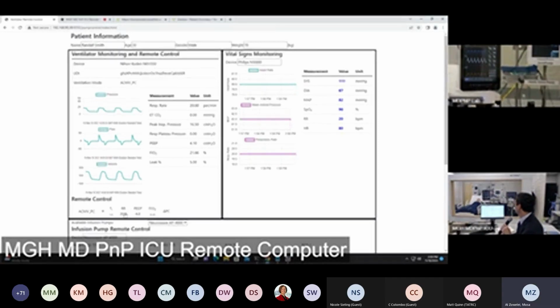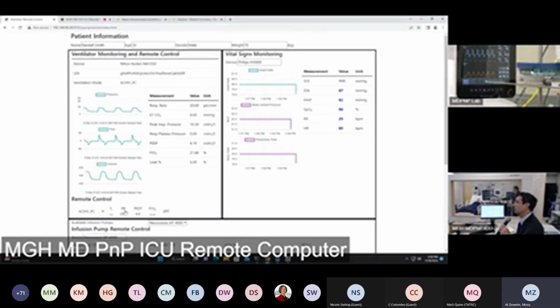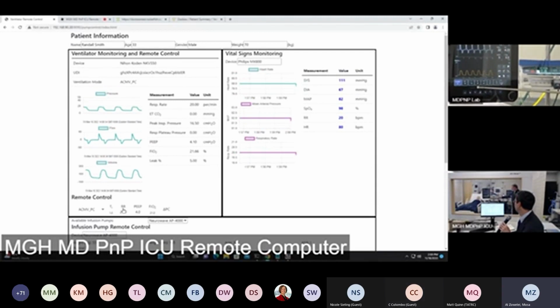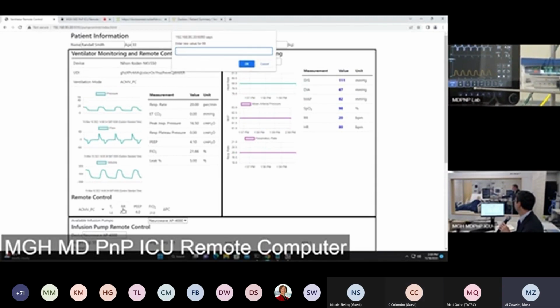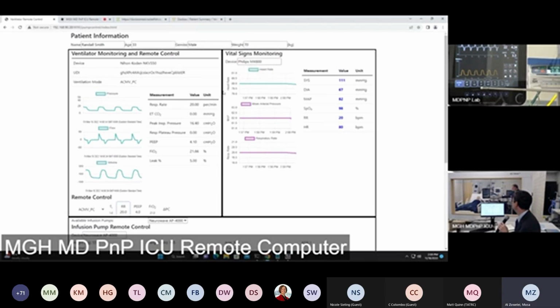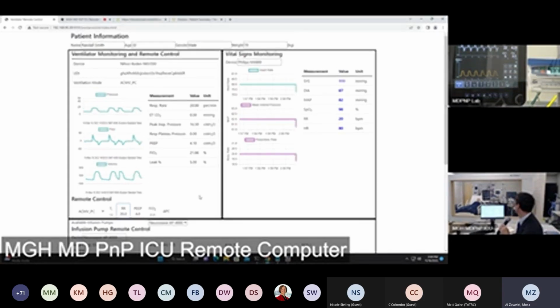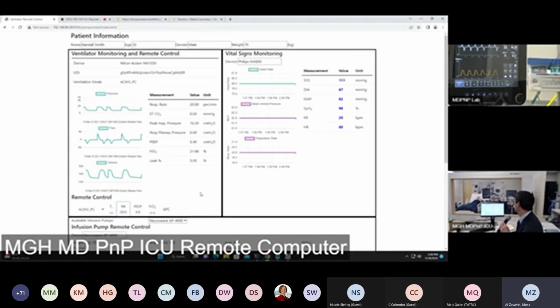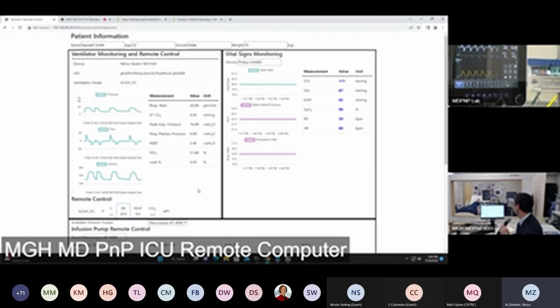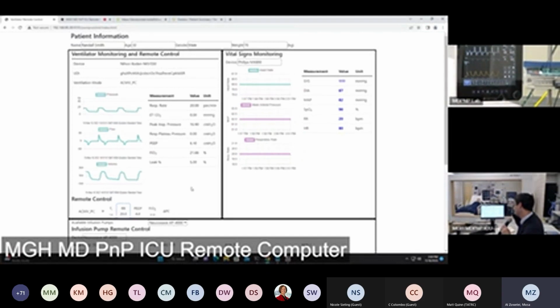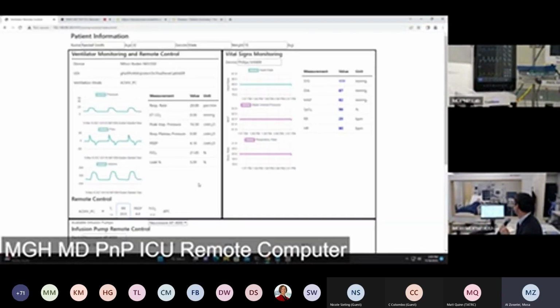I'm going to adjust the respiratory rate. So it's currently set to a respiratory rate of 20. You can see that on the remote control display here, and we can see it on the ventilator screen right there in the bottom in the middle, RR 20. I'm going to change that to 17. I type it in, press OK, and immediately see that change on the ventilator, and it's now running at a respiratory rate of 17. We have that capability with several other parameters where we're able to set that and remotely control it. We can also see all the waveforms from it simultaneously.